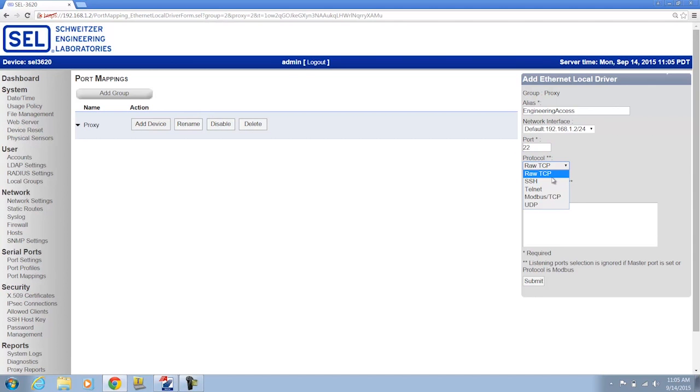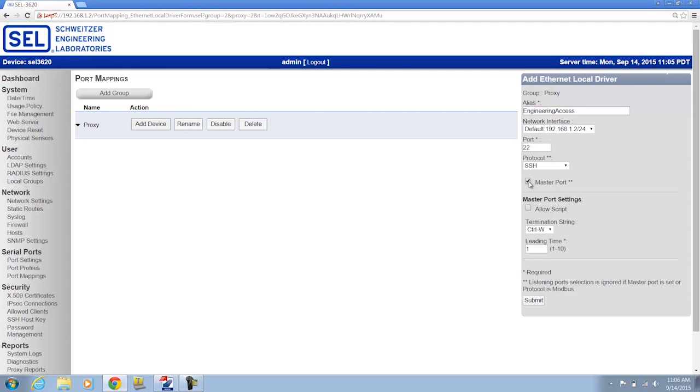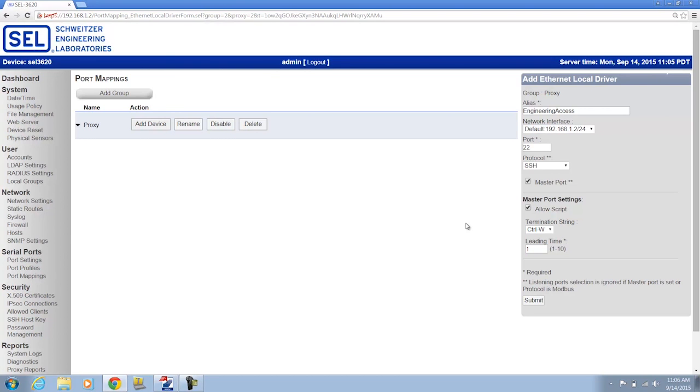Protocol, I'm going to choose SSH. And then the important part that actually allows me to access this relay is I'm going to click the Master Port option. Now, under Master Port Settings, I'm going to check it to make it a scripting-enabled master port. And this is the special sauce that allows you to look at the group privileges, select the relay, and enter various access levels without an engineer needing to know what the relay passwords are.